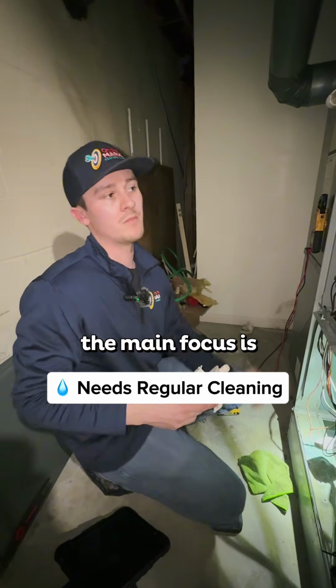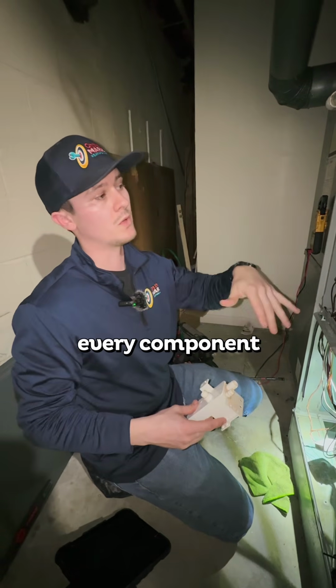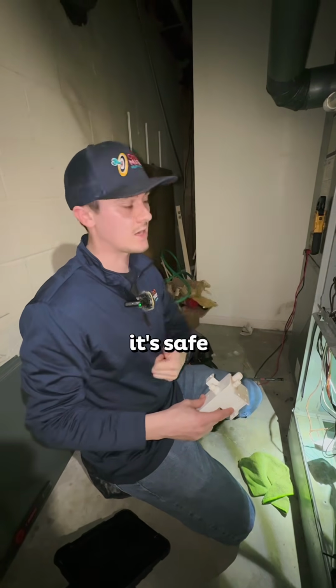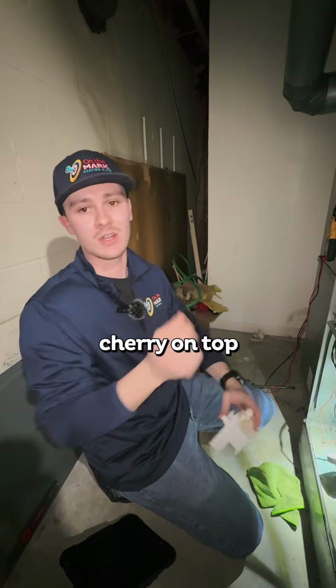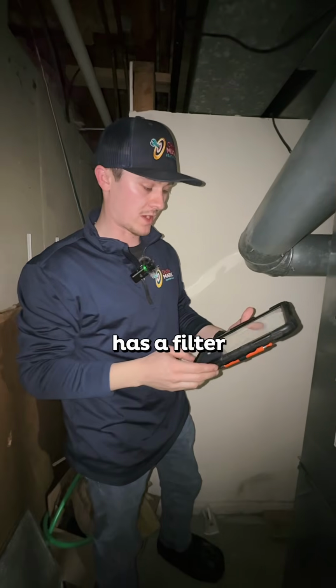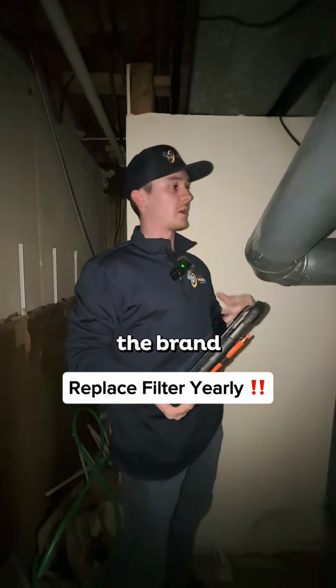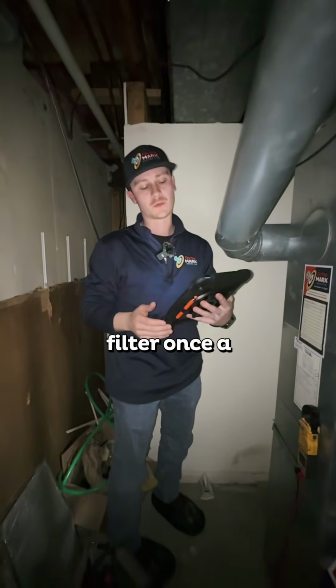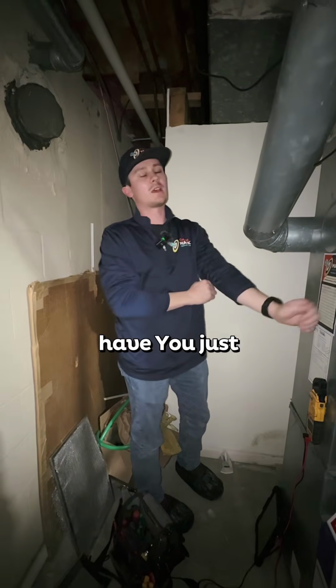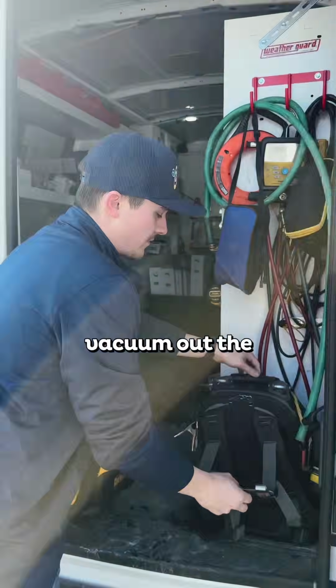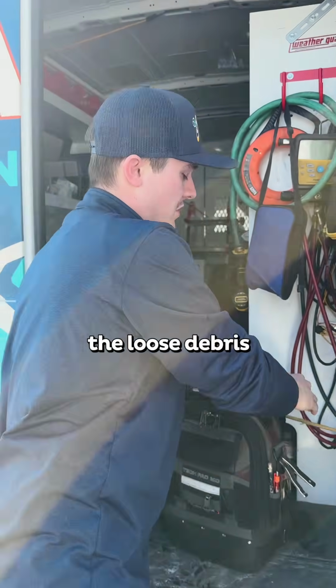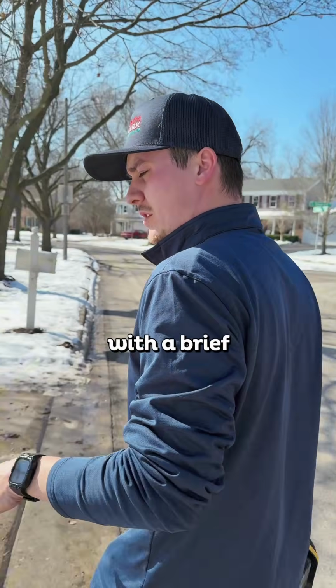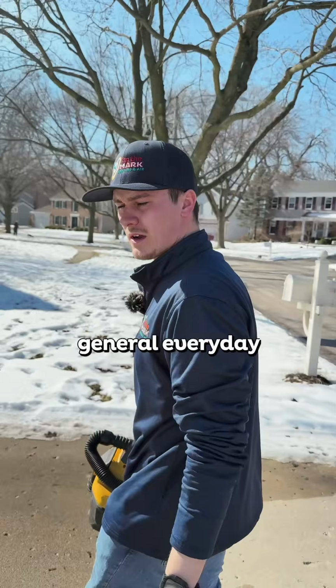When it comes to a tune-up, the main focus is checking each and every component, especially the heat exchanger, and making sure it's safe, it's running properly. Cleaning is just kind of the cherry on top. It's not the main focus. The humidifier has a filter inside. Aprilaire, the brand we work with, they recommend replacing that filter once a year. Humidifiers, they're very, very nice to have. You just have to keep up with the maintenance. We are going to vacuum out the system, get all the loose debris out of there, and then I'll follow that up with a brief spray and wipe down with just some general everyday cleaner, nothing crazy.